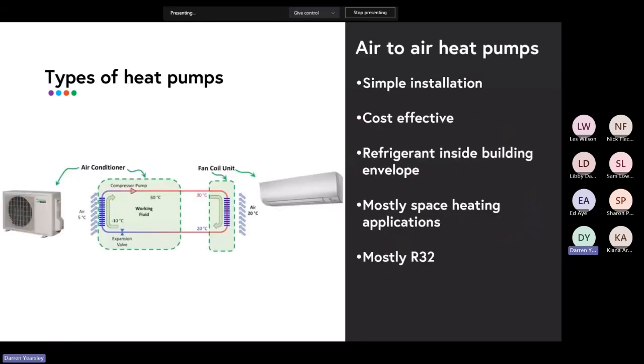Okay, so when most people, the retail masses, think about heat pumps, almost always they're thinking about air-to-air heat pumps. So you have an outdoor unit, and then you have an indoor unit which blows hot or cold air. These type of heat pumps are very simple to install, and very, very cost effective. But some of the limitations with them are that you're bringing refrigerant inside the building envelope, it's mostly only used for space heating applications, and it's mostly R32.